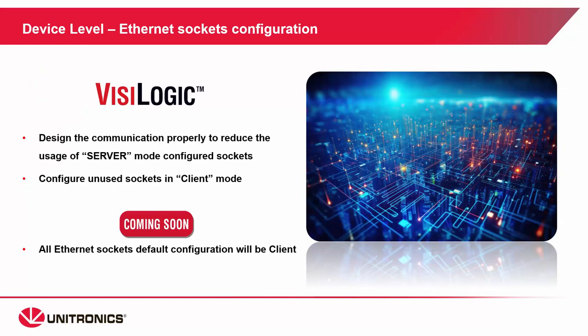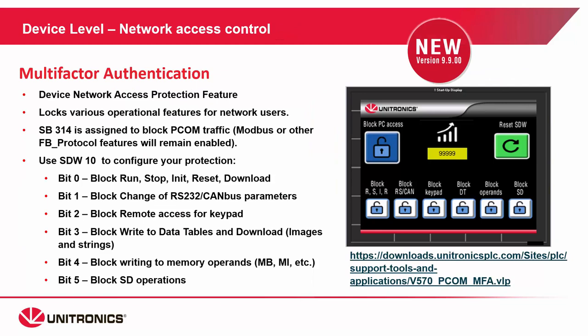When possible, reduce the number of sockets you have set to server mode. When you're considering your network infrastructure, set any unused sockets to client mode — this way they will not be remotely accessible. Coming soon, in a new version of VisiLogic, all Ethernet sockets will have the default of client.